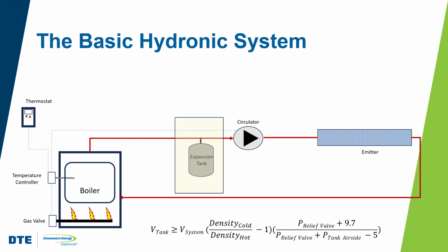Now, often tanks are pre-pressurized by the manufacturer to 12 psi. That's a pretty common number, and oftentimes installers may think, okay, that's close enough to what it's normally going to be for a house with 3 stories, including the basement where the boiler typically is. But we actually should adjust that air pressurization, right? It should be adjusted to the actual calculated value based on the actual job site conditions, right? By doing that, we are assured that the diaphragm will be fully expanded when the system is filled, but not heated.